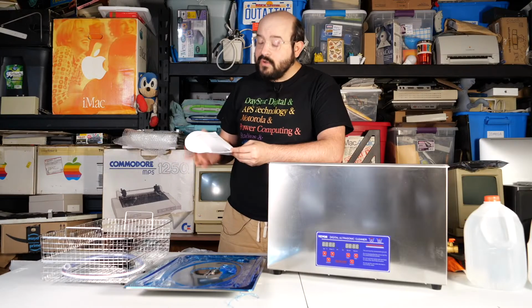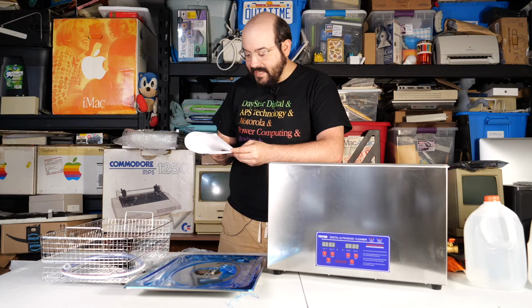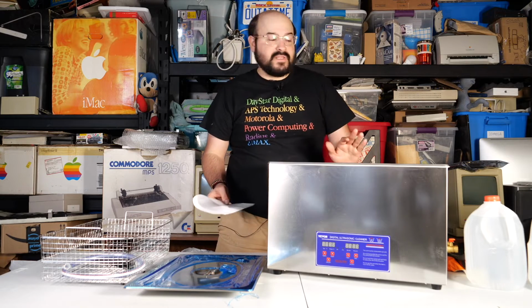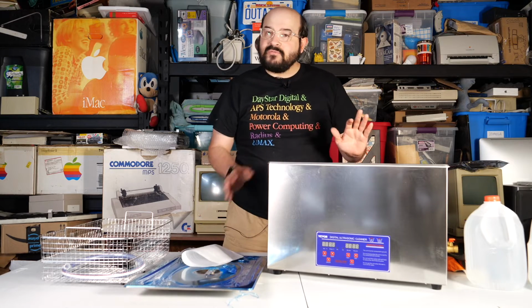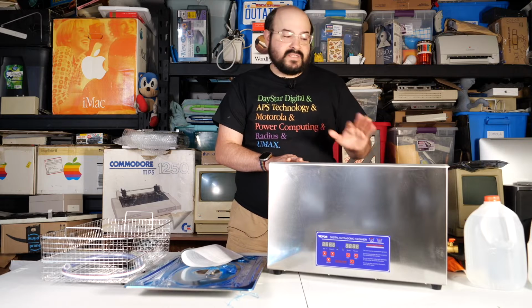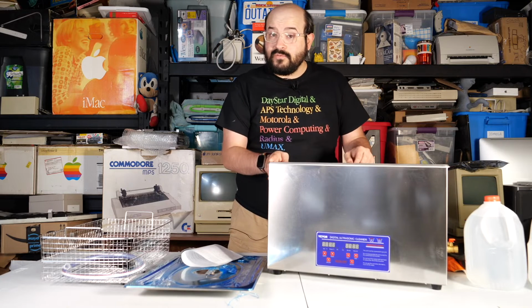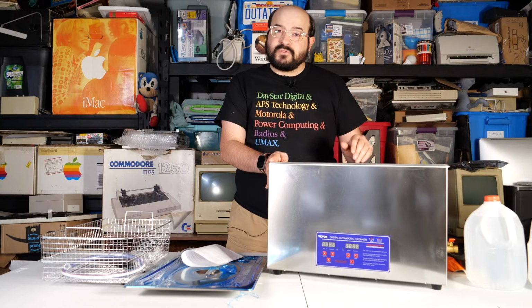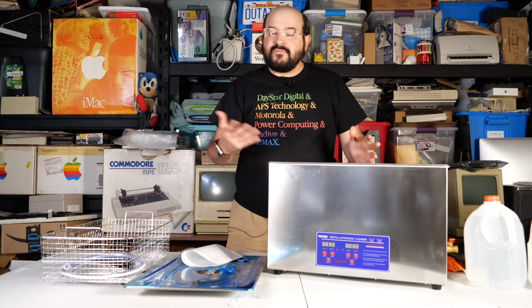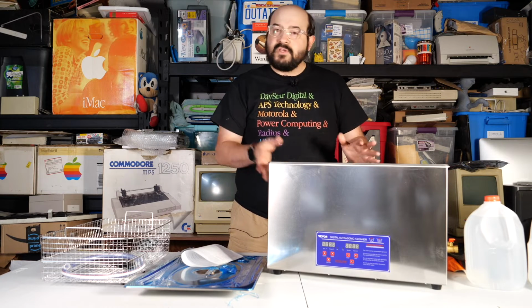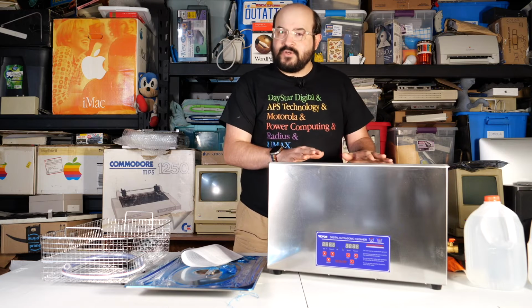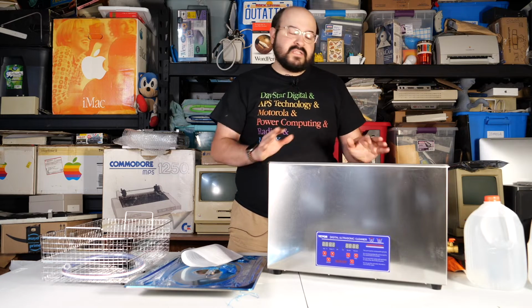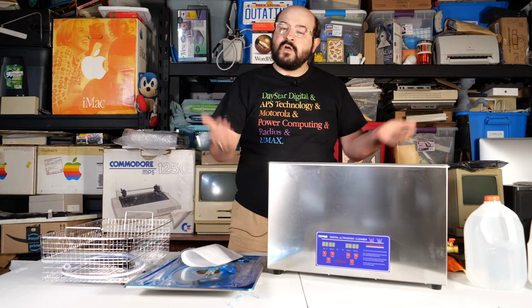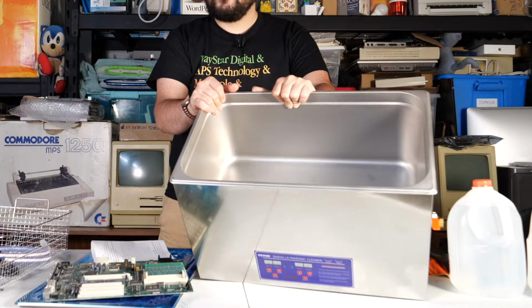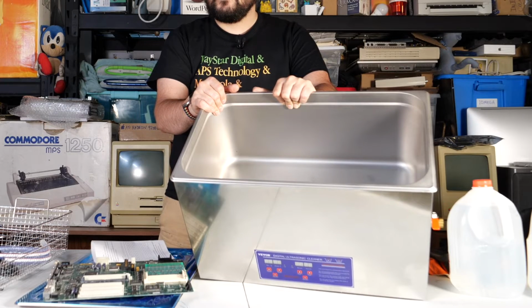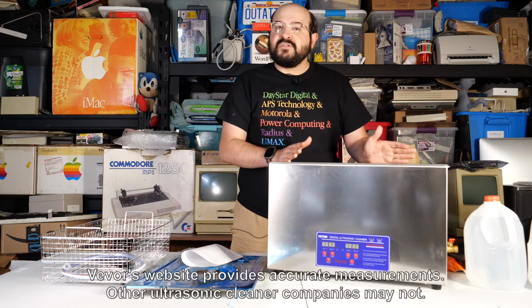The specifications also talk about the tank size and capacity. This tank is rated for 30 liters, however I do not think you could safely fill it with 30 liters—you'd have some overflowing. But that's usual in ultrasonic cleaners; they'll rate it for 10, 15, 20, or 30 liters, but you'd be hard pressed to actually fit that volume of liquid in the tank. This is because the tanks are usually curved or tapered on the sides or edges. Even some of the measurements you see in manuals or online don't take into account these curves.